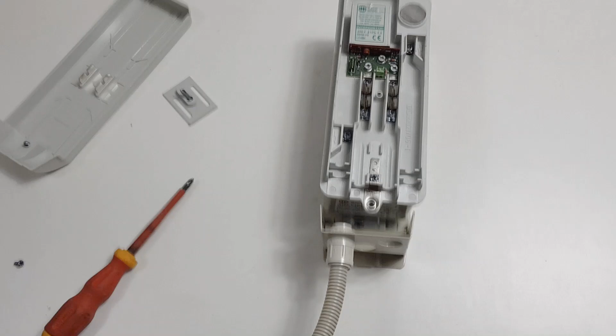So I've got my conduit, one section in, and you do this for all 3 - for your power cable, but also for both of your HT. A big problem that guys often get repair call outs on is when people join or cable tie the HT cable to one another, when the HT cable can't go near anything metal. It's not like normal power wire where you can just hook it up and put a saddle clip on it and hope for the best, or strap it or cable tie it to itself. It doesn't work like that.